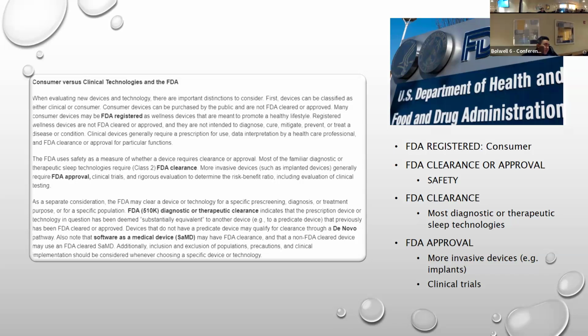And clearance versus approval, well, basically the biggest measure is safety. So if it's something fairly non-invasive, like a diagnostic or even a therapeutic device, a home sleep apnea test or whatnot, they're non-invasive and typically carry a lot less risk in terms of safety. They need to have FDA clearance, and then FDA approvals will be for something more invasive. So for example, if you want to implant something into someone, that will need an FDA approval. And then that will require many more clinical trials and all that before it can hit the market.